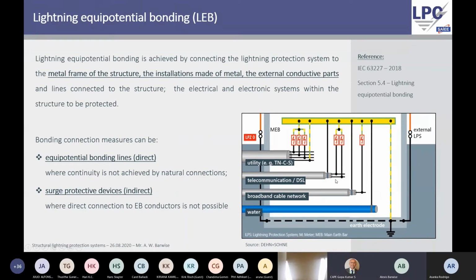And that is something I so often see, that people do not understand that surge protection devices, as a first principle or first measure, are actually there to ensure lightning equipotential bonding between live parts and the earthing system itself.